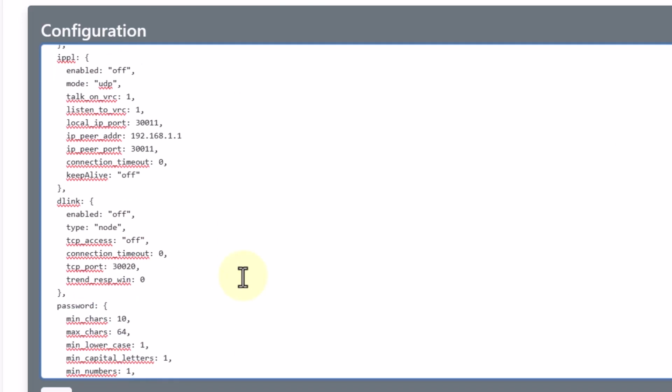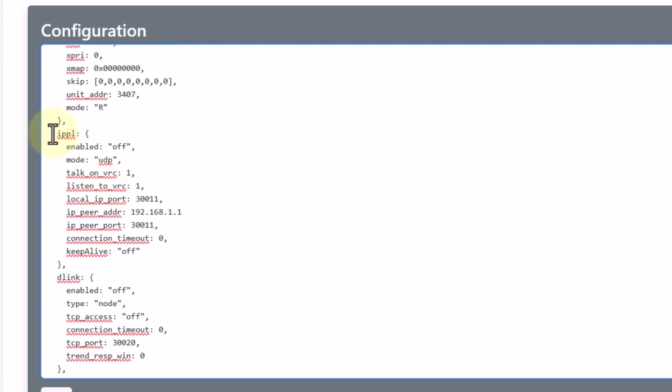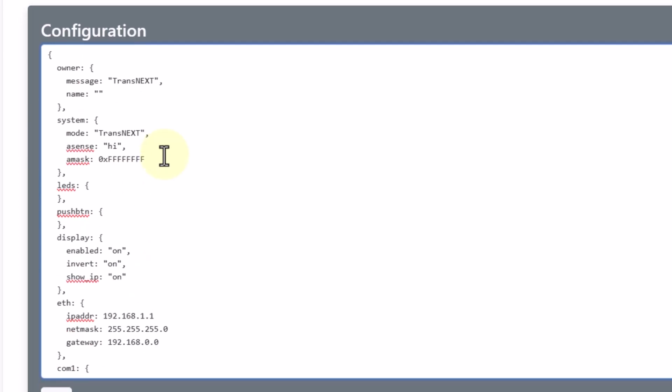And you can see here where the Ethernet, the IP payload is what that stands for, is an option here. So this would be a completely full TransNEXT system. So if you're doing one from scratch, this would be the way to go. This is going to operate similar to the SD's Ethernet over the air. The idea here is that these are long range systems. So we do basically serial payload or IP payload over the air to minimize the amount of overhead for that Ethernet traffic, and it keeps the robustness of the TransNEXT system kind of in place.